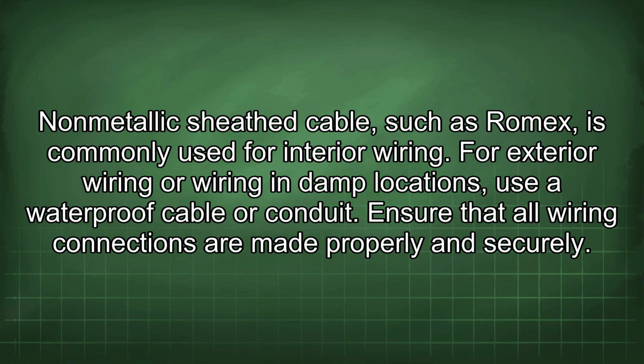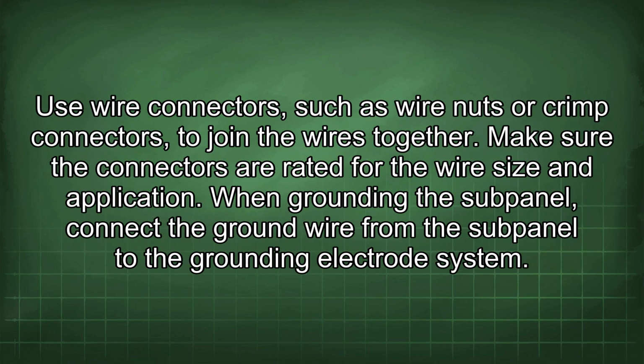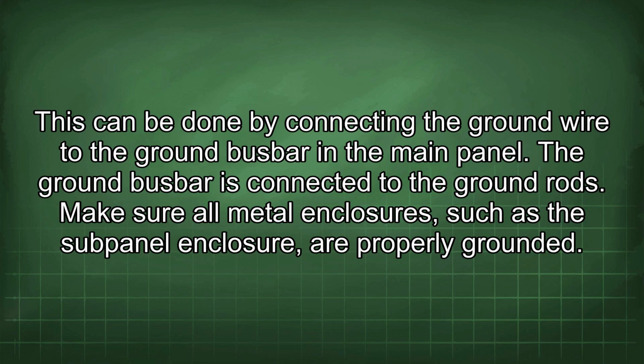Ensure that all wiring connections are made properly and securely. Use wire connectors, such as wire nuts or crimp connectors, to join the wires together. Make sure the connectors are rated for the wire size and application. When grounding the subpanel, connect the ground wire from the subpanel to the grounding electrode system. This can be done by connecting the ground wire to the ground busbar in the main panel. The ground busbar is connected to the ground rods.